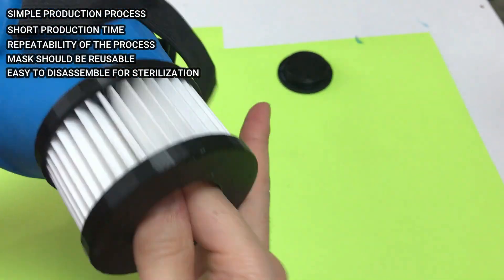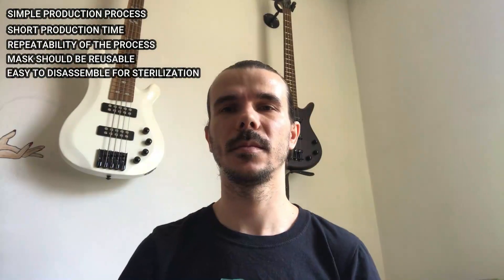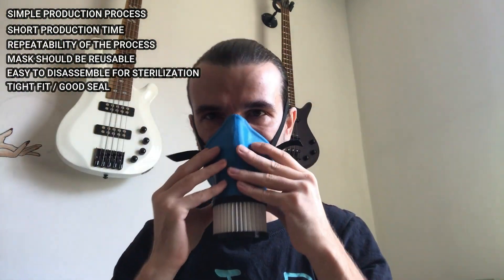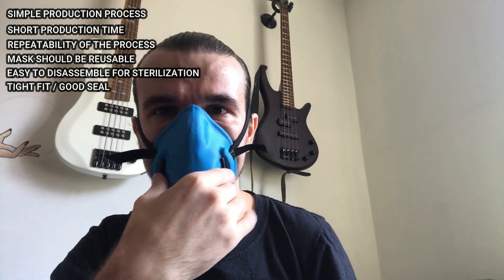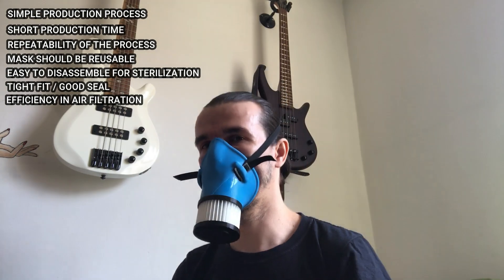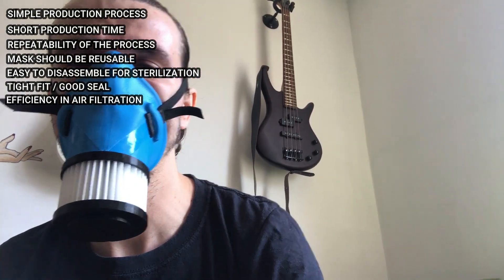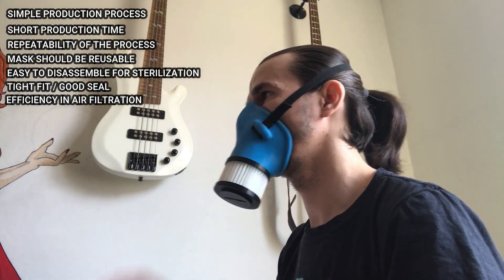Masks should be easy to disassemble for individual sterilization of each material. The mask should fit tightly and make a good seal on various face configurations. Silicone rubber has this quality. Filter should offer protection equal or better than N95 masks. The tight seal and the H13 HEPA filter should provide 99.97% efficiency in air filtration.